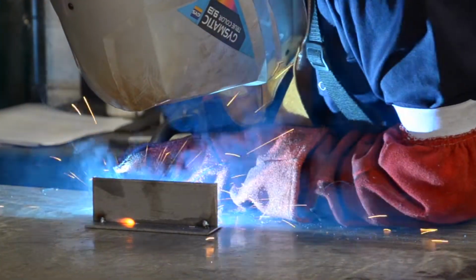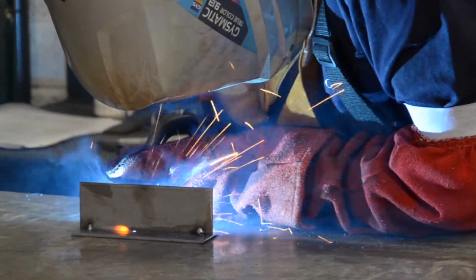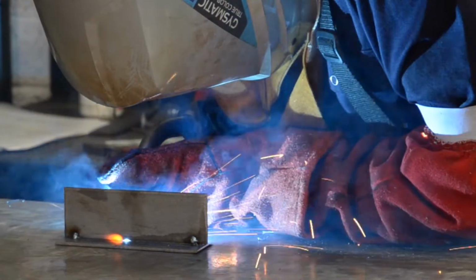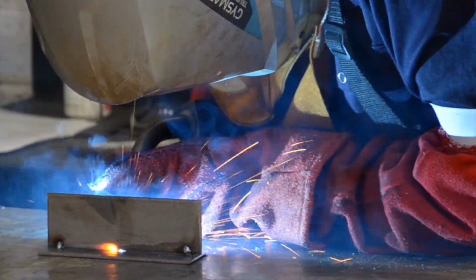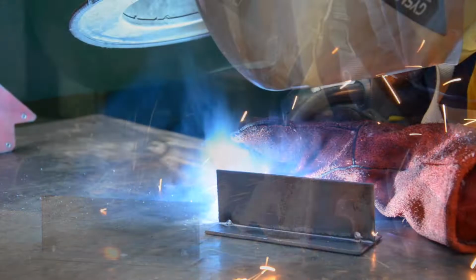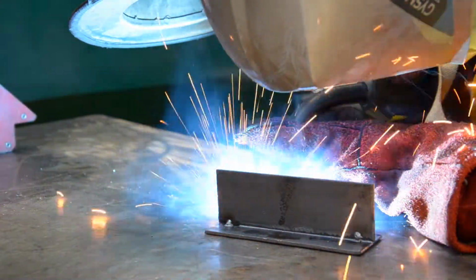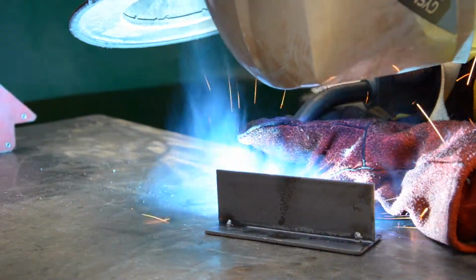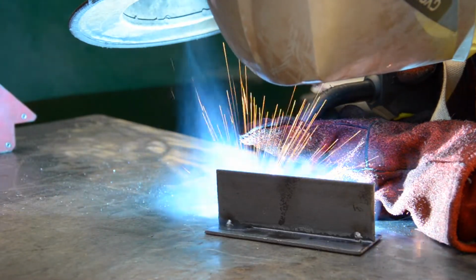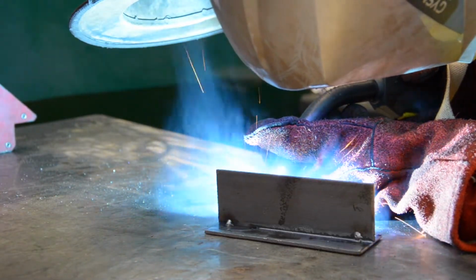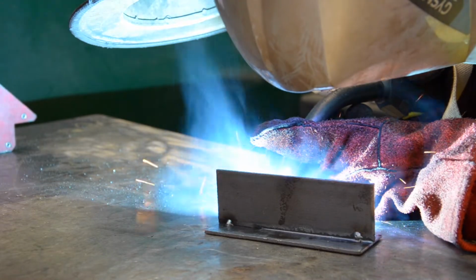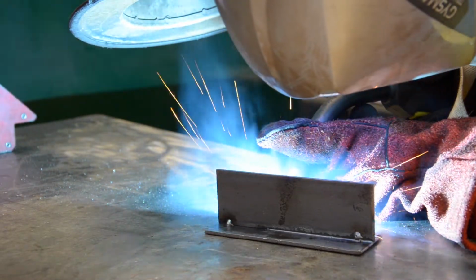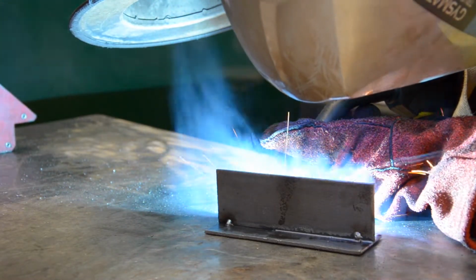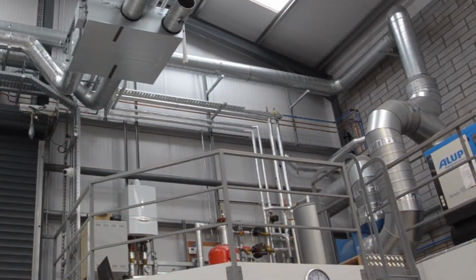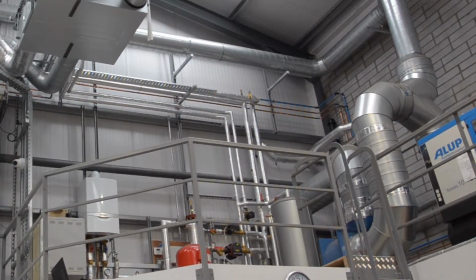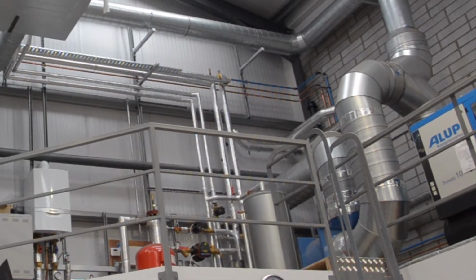With no extraction, the welding fumes are free to flow around the welder's helmet, exposing the worker and others to harmful fumes. With the extraction in operation, the fume is extracted via the ductwork to the filter. For maximum benefit, the local exhaust ventilation or LEV hood should be set as specified in the commissioning report. The filter in the fan unit removes the dust, preventing it from going into the atmosphere.